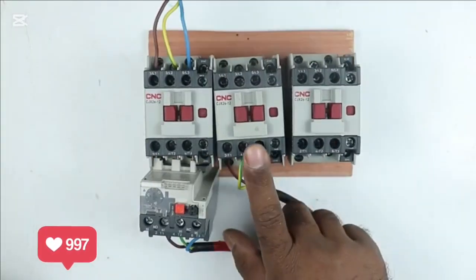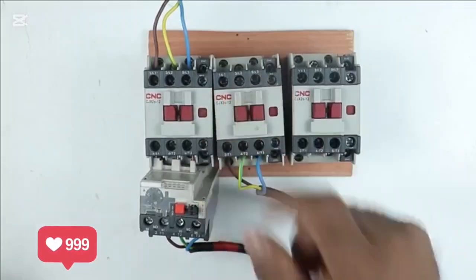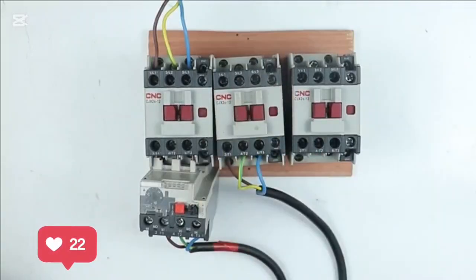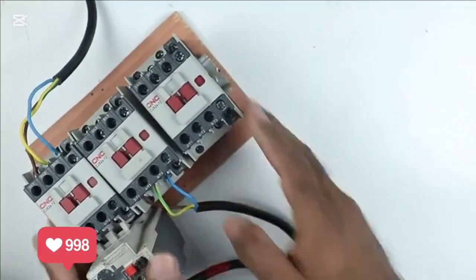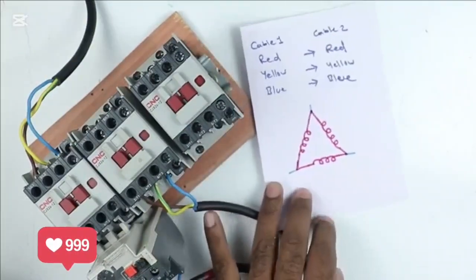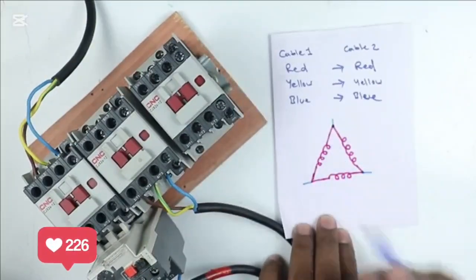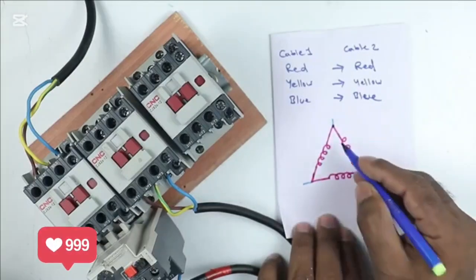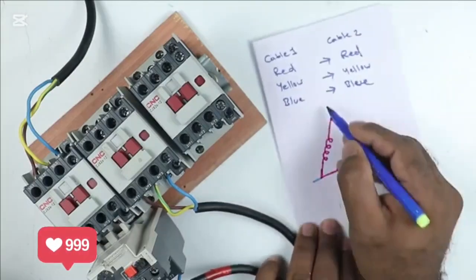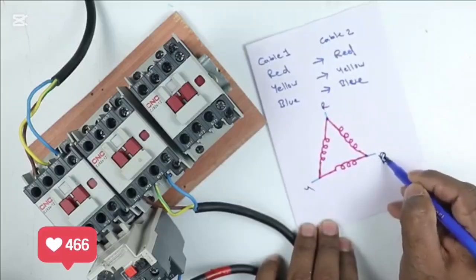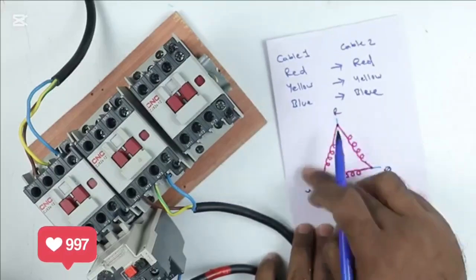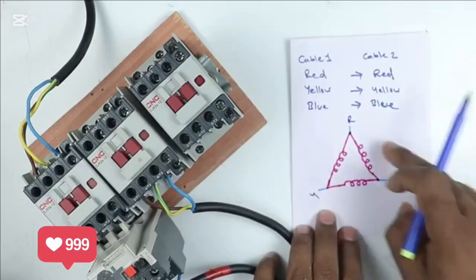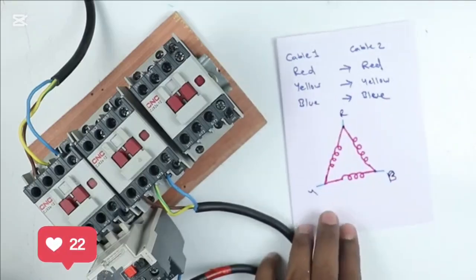Now in this delta contactor, at the time of connection at input terminals, you have to keep one thing in mind. What is that? Listen carefully. I am keeping this aside. The drawing I have, in this drawing, look at this symbol. This is of delta connection. If you only want to run the motor in delta connection, then connect the motor winding in this way. And simply R, Y, B phase power supply has to be connected here. If you provide these three phase power supply to these three terminals, then your motor will start.